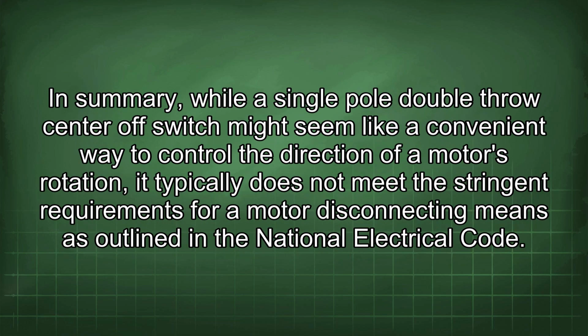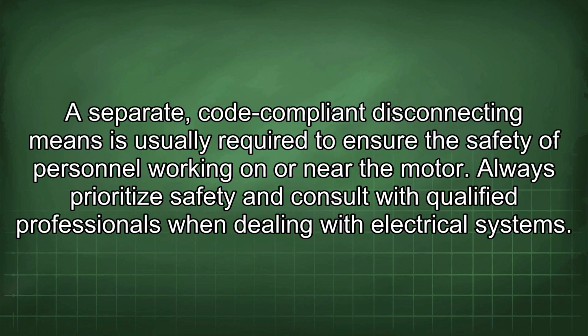In summary, while a single-pole double-throw center-off switch might seem like a convenient way to control the direction of a motor's rotation, it typically does not meet the stringent requirements for a motor disconnecting means as outlined in the National Electrical Code. A separate code-compliant disconnecting means is usually required to ensure the safety of personnel working on or near the motor. Always prioritize safety and consult with qualified professionals when dealing with electrical systems.